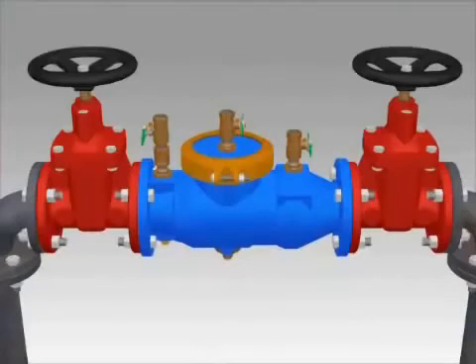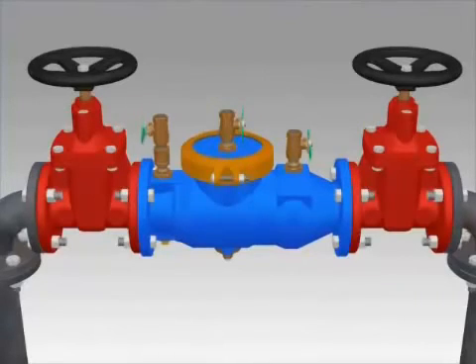Close the number 3 test cock. Open your inlet valve slowly to pressurize the assembly. Inspect for any leaks. Open and then close test cocks to bleed air from the assembly. Open your outlet valve a small amount and wait for the system to pressurize. Fully open the outlet valve once the system is pressurized. Valve should be tested by trained personnel to confirm that it is working properly.